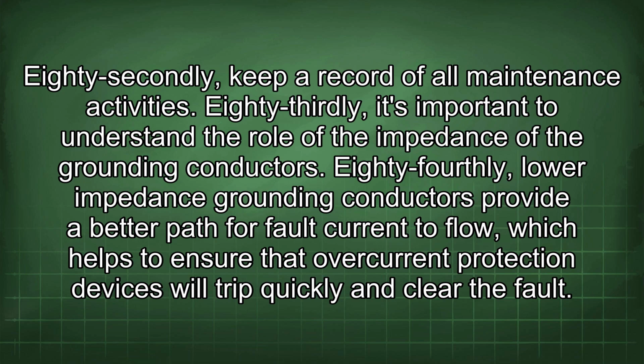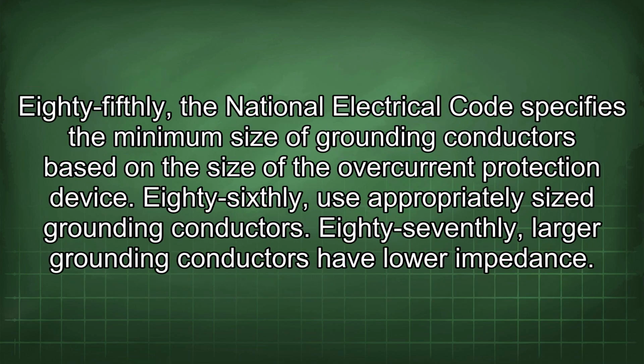83rd, it's important to understand the role of the impedance of the grounding conductors. 84th, lower impedance grounding conductors provide a better path for fault current to flow, which helps to ensure that overcurrent protection devices will trip quickly and clear the fault. 85th, the National Electrical Code specifies the minimum size of grounding conductors based on the size of the overcurrent protection device. 86th, use appropriately sized grounding conductors.